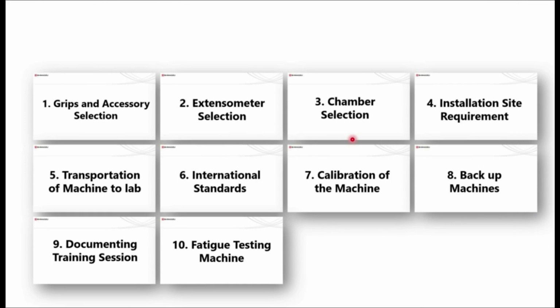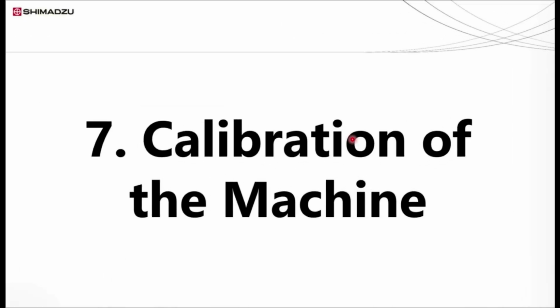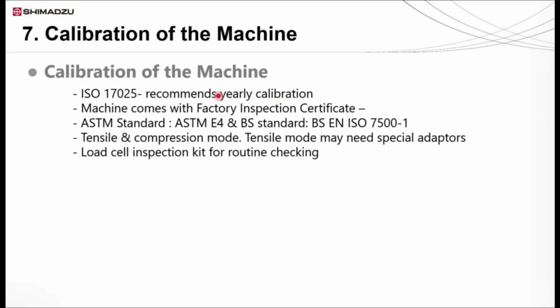Moving on to the next point, calibration of the machine. This is another point where many customers always ask our advice. ISO 17025 recommends yearly calibration of a universal testing machine unless otherwise specified. The standard also recommends that once the machine is moved, repaired or adjusted, the previous calibration is invalid. So after installation, calibration is a must even though it is a brand new machine. So upon getting the machine in your factory, please recalibrate it on site to comply with the ISO 17025 requirement.